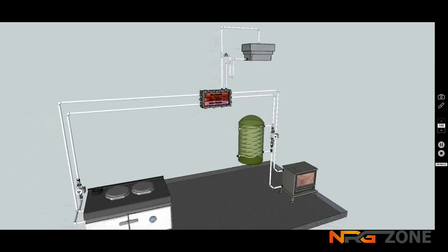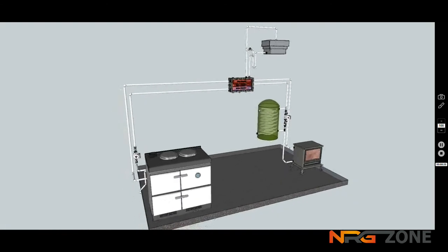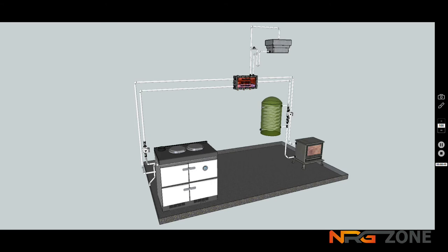A condensing cooker needs the coldest water in the system in order to condense. So, this is the Stanley-Brandon cooker, and in this situation, for its internal mechanism requires that the return would be put into a higher port than the flow. So the pump would take the coldest water in the system, which is coming back from the zones, and push that water into the cooker, be heated by the cooker, but of course any condensate caused then would be at a maximum level because it's the coolest water in the system, and the flow would come back out and go into L1.